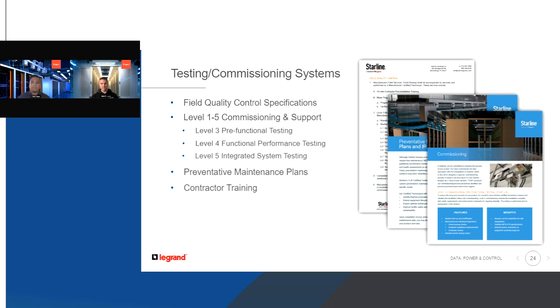We reach out to you and say, from the testing and commissioning side, don't lack on that. From a specification standpoint, how we can help you as spec engineers, end users, and clients is that we've developed field quality control specifications for you to follow, and it's very important to do that. Once the busway is delivered and installed, you don't want the installing contractor essentially checking their own work. It's good to have them overseeing things, but I always recommend - whether it's Starline or other vendors, your UPSs, your PDUs - always have somebody there from the manufacturer who knows their systems better than anybody else, for the levels of commissioning.